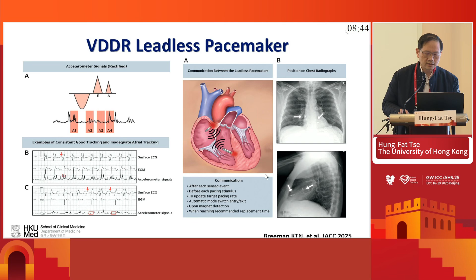If you look at the Aveir ventricular device, it mainly has one big screw and a dome. But if you look at the atrial device, they actually have two helixes. So this is one of the reasons why after the implant they tend to have a much lower impedance. But also the internal helix actually facilitates the fixation of that device in the atrium. So this is a kind of unique device.